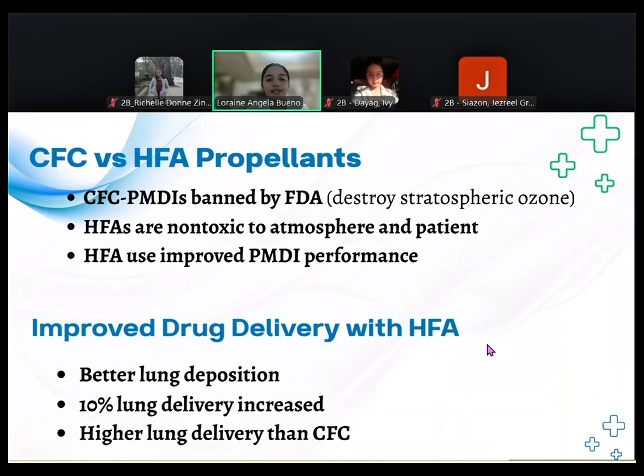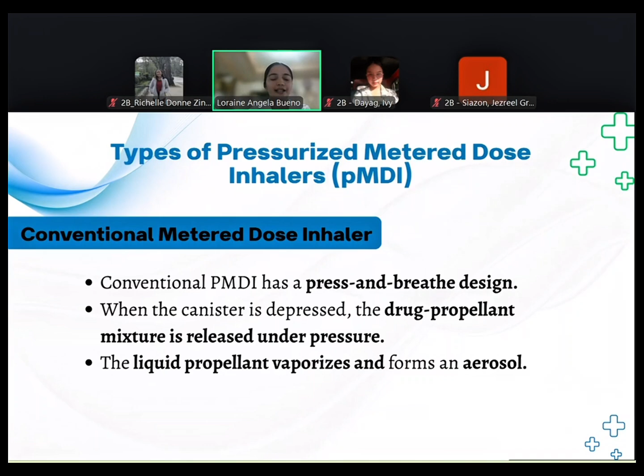The conventional metered dose inhaler has a press and breathe design. When the canister is depressed, the drug propellant is released under pressure. The liquid propellant is vaporized and forms an aerosol. So the conventional metered dose inhaler has a press and breathe design, which means you press the canister as the patient breathes in. When the canister is pressed, the drug propellant mixture comes out under pressure, and the propellant vaporizes. Its rapid expansion is the reason the drug becomes aerosolized.